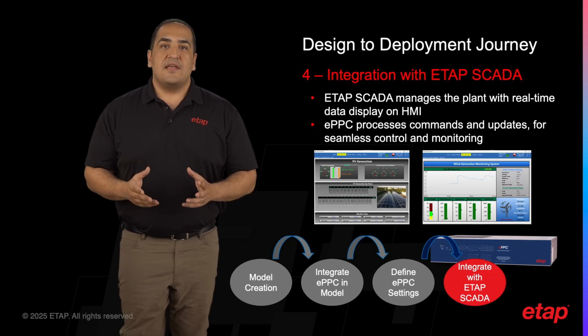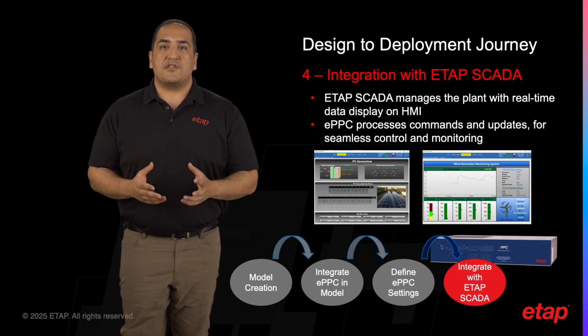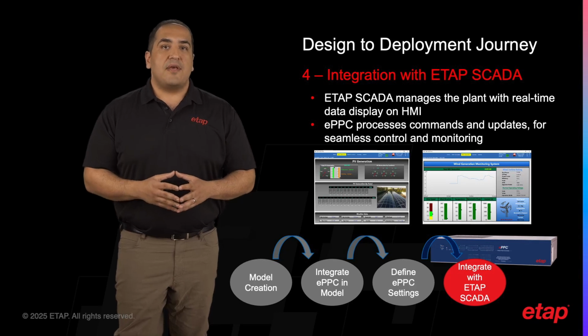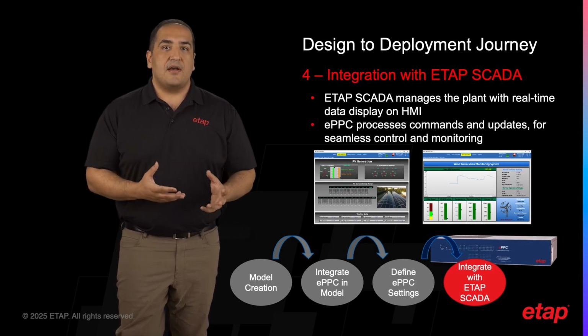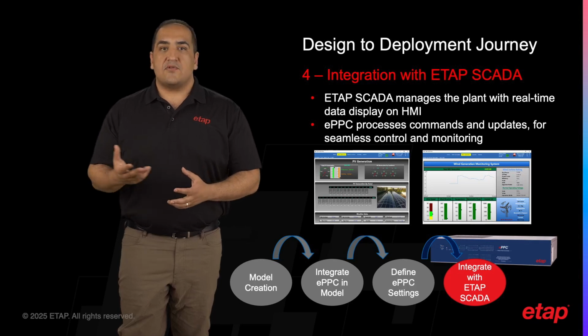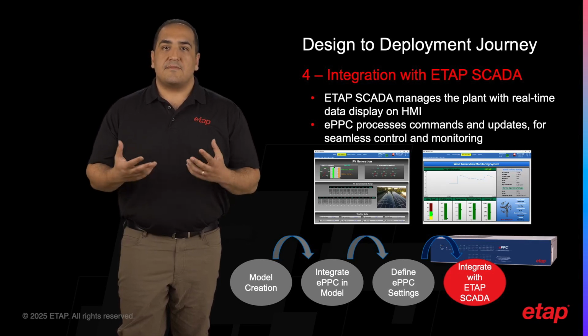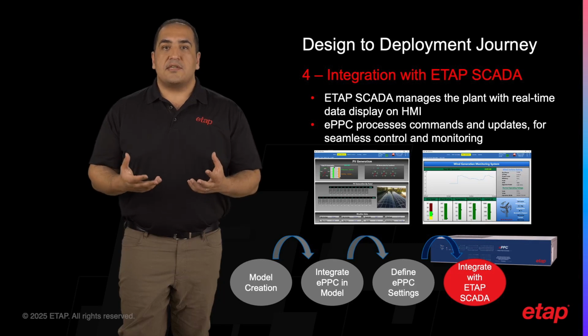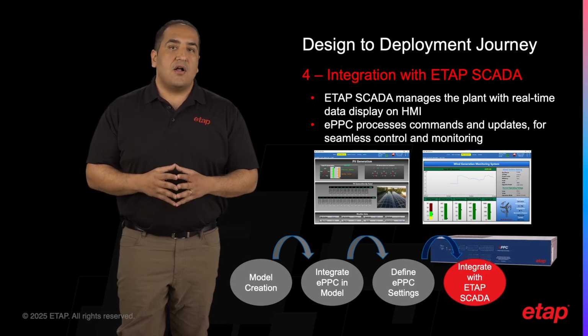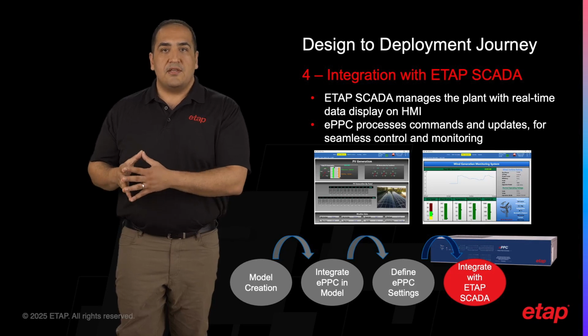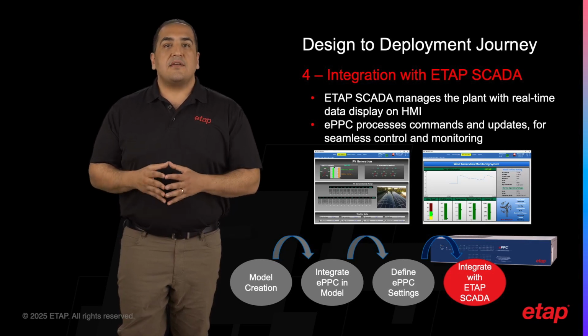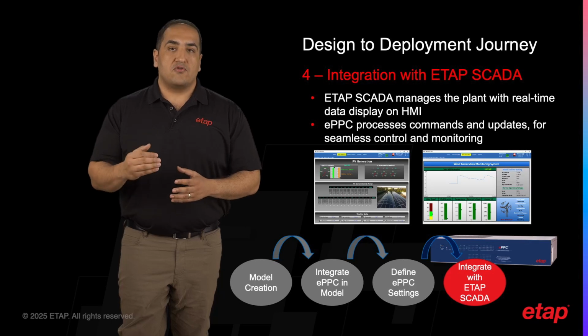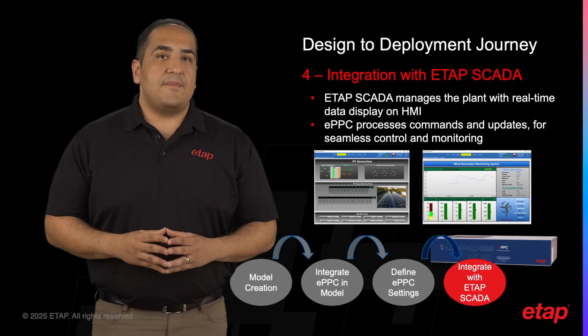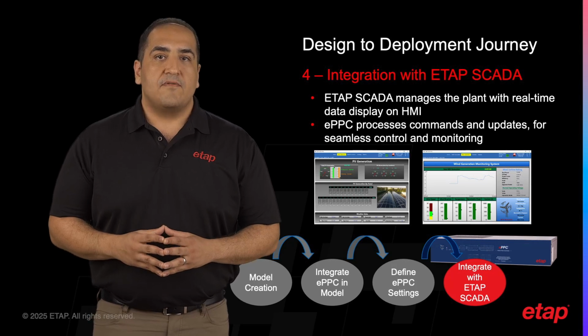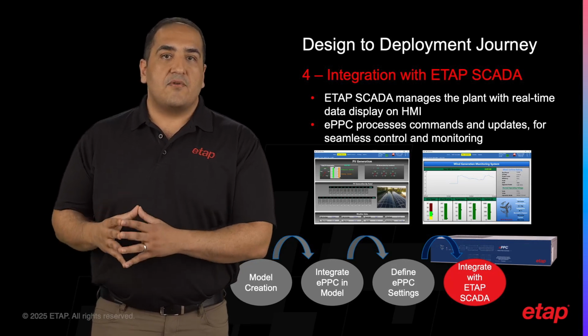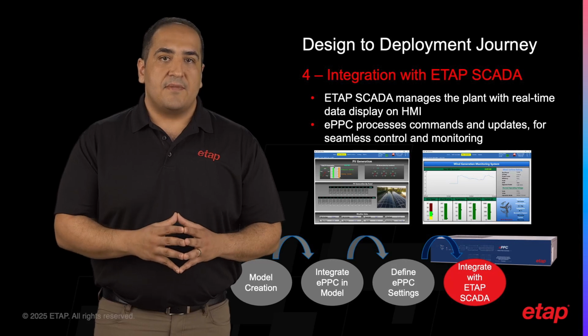During the operational phase, ETAP's SCADA solution is used to manage the plant. An HMI is developed based on the plant's model, with ETAP SCADA acquiring real-time data from various sources such as breakers and meters and displaying this information on the control center's HMI. This data is also fed into EPPC, where the internal logic, controller settings, and commands from the operator or higher layer controller are processed. EPPC then generates the necessary commands, which are relayed back to SCADA and subsequently sent downstream to relevant assets.